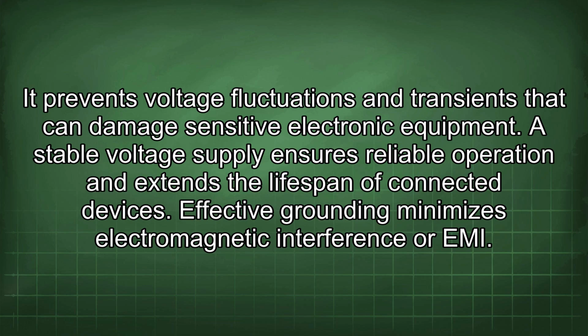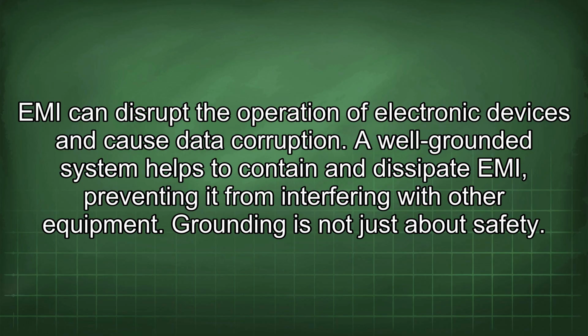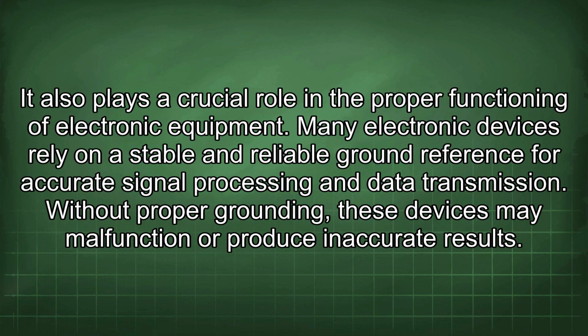Effective grounding minimizes electromagnetic interference, or EMI. EMI can disrupt the operation of electronic devices and cause data corruption. A well-grounded system helps to contain and dissipate EMI, preventing it from interfering with other equipment. Grounding is not just about safety. It also plays a crucial role in the proper functioning of electronic equipment. Many electronic devices rely on a stable and reliable ground reference for accurate signal processing and data transmission. Without proper grounding, these devices may malfunction or produce inaccurate results.